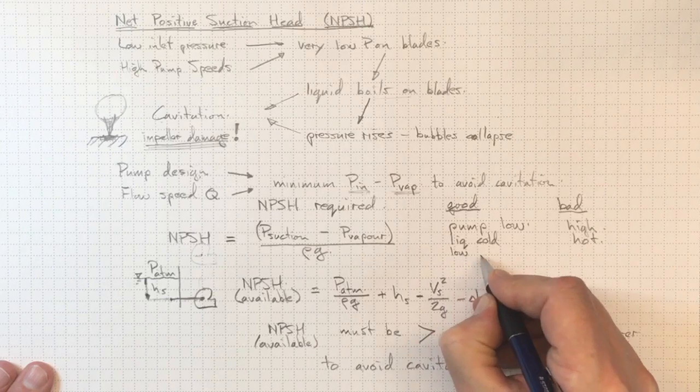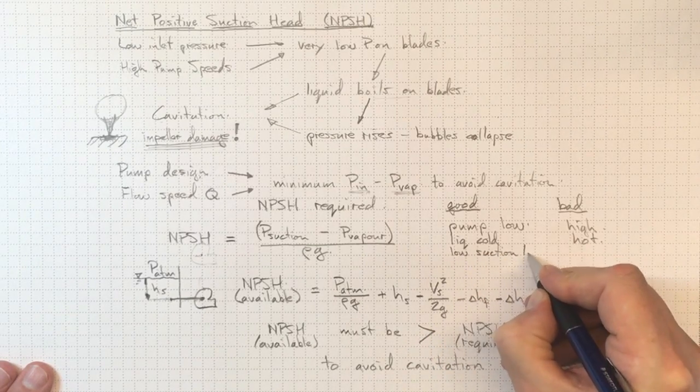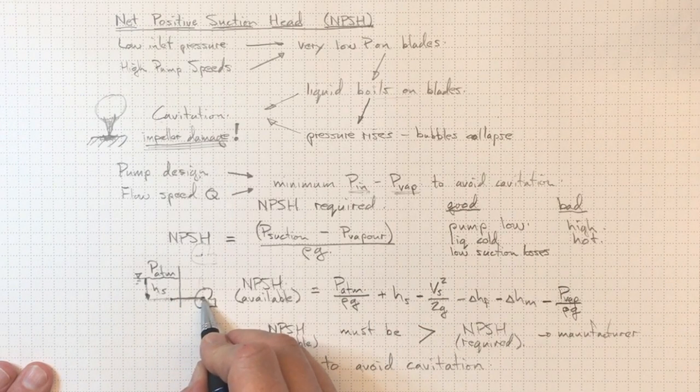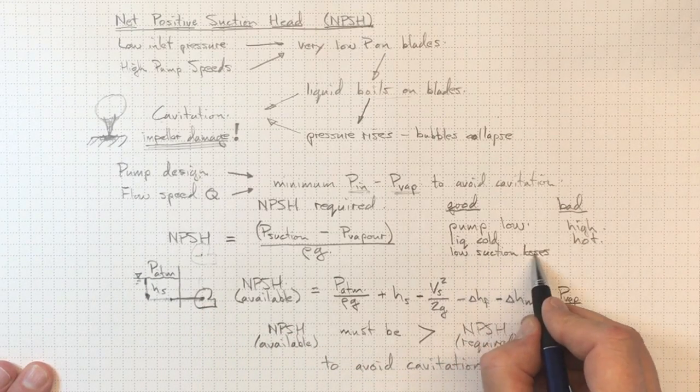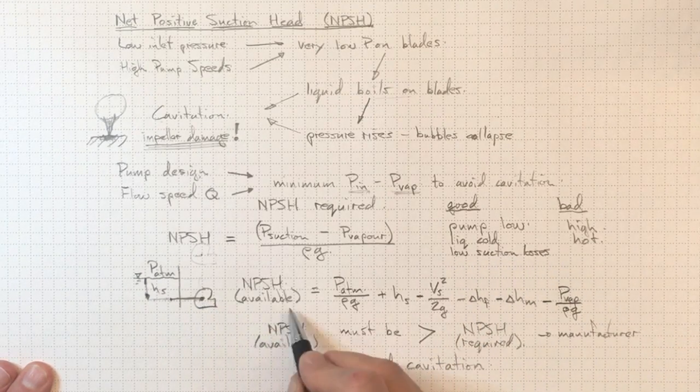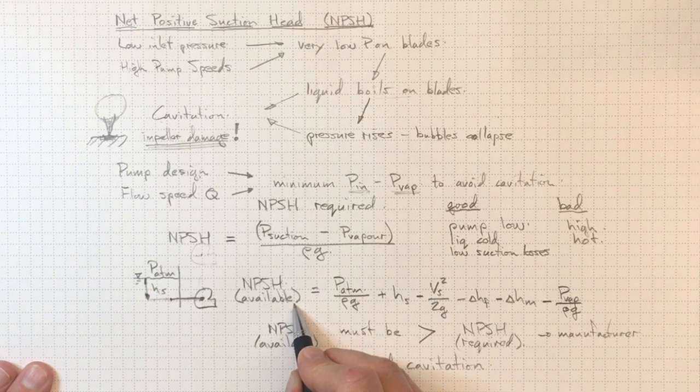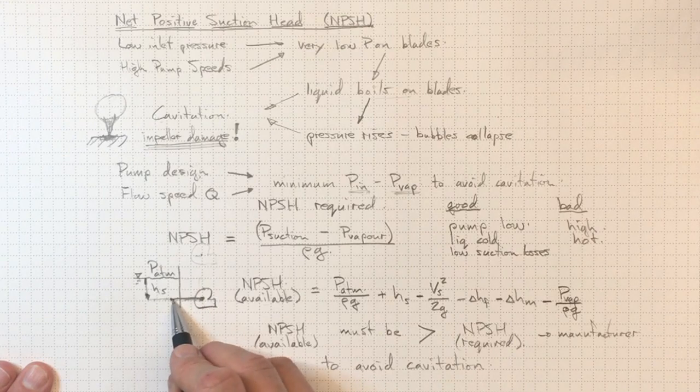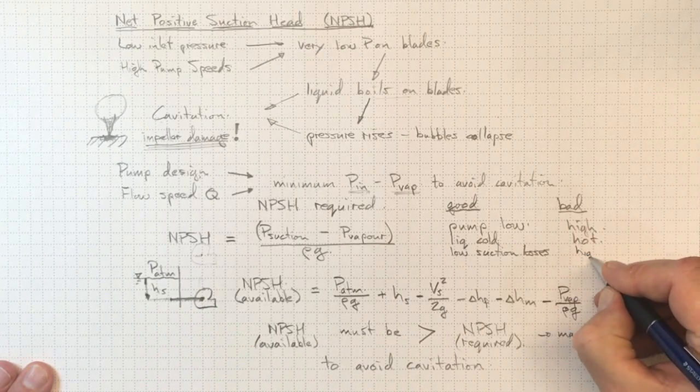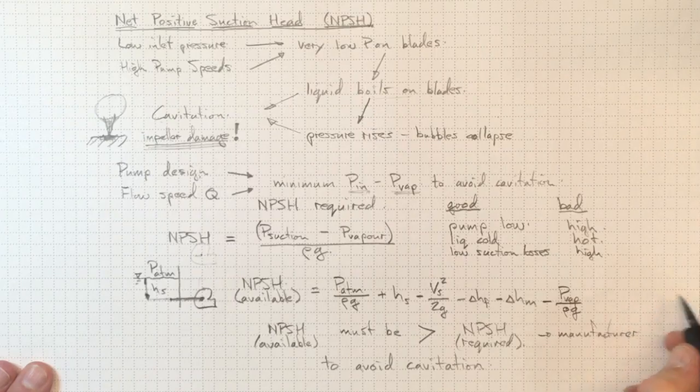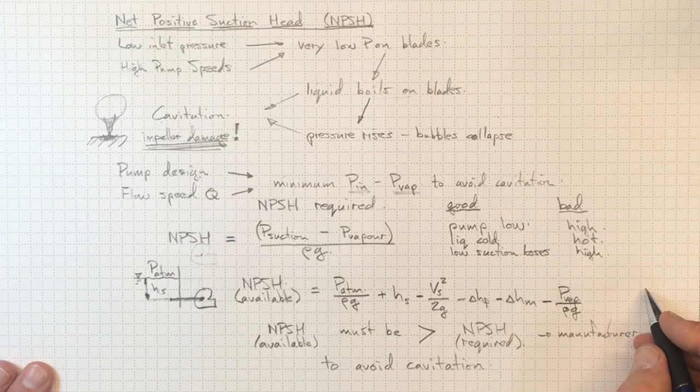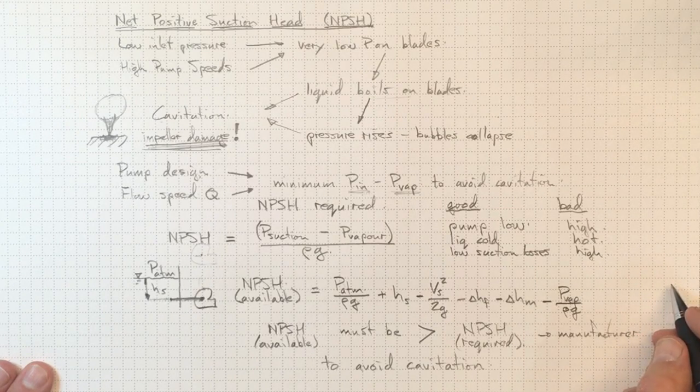Low suction losses will be good. If we've got a short pipe, that'll be good. If we manage to avoid having a whole lot of fittings and valves on the suction side, that'll be good. Anything that allows us to have low suction losses is going to increase the pressure and increase the NPSH that we've got available. On the other hand, bad. A long length of pipe there with a whole lot of fittings in it, we'd have high suction losses and we could run into NPSH problems. We could get cavitation and wind up damaging our impeller and reducing the life of our pump quite significantly.